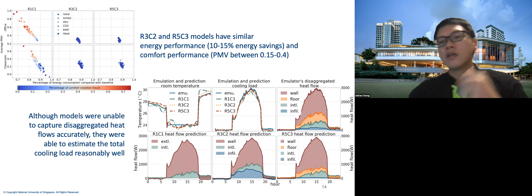This figure on the top left summarizes the control performance. At a glance, the R3C2 and R5C3 models have very similar performance. We are seeing energy savings compared to baseline of around 10 to 15%, and average PMV between 0.15 to 0.4. The percentage of comfort violation hours, meaning the number of hours where the predicted mean vote exceeds plus minus 0.5, also stayed within the 10% range.